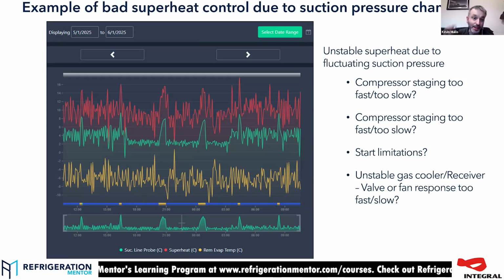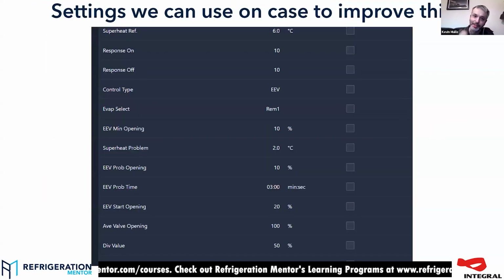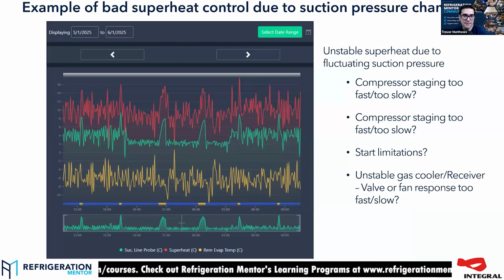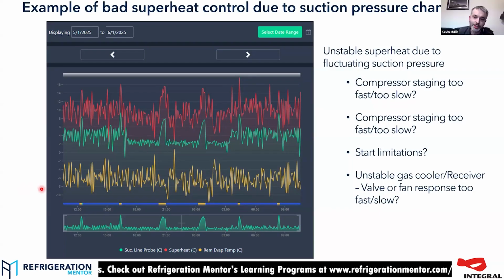So the flip side of the superheat control: is it due to the suction pressure changing? So on this graph, you can see the suction line probe, especially if you look over the night period in the middle there, pretty stable. The evaporating temperature, pretty all over the place. So what's causing that to happen? Are the compressors moving too fast? Are the compressors moving too slow? So that's the yellow line at the bottom there. That's your evaporating temperature.